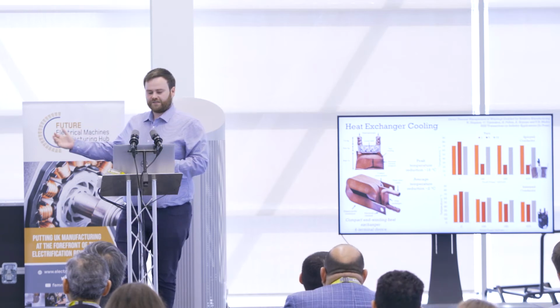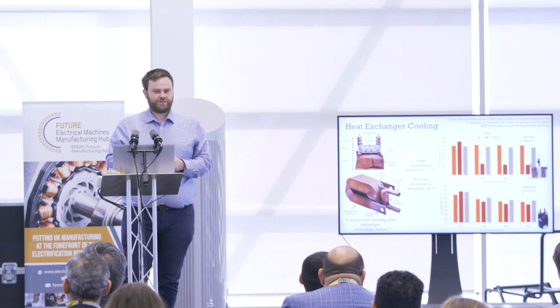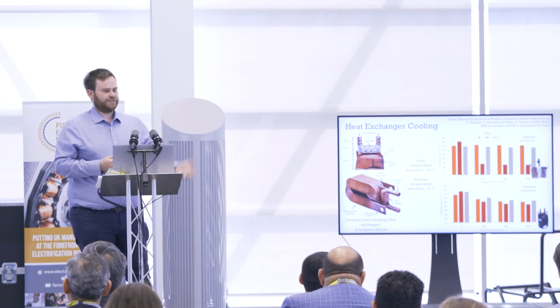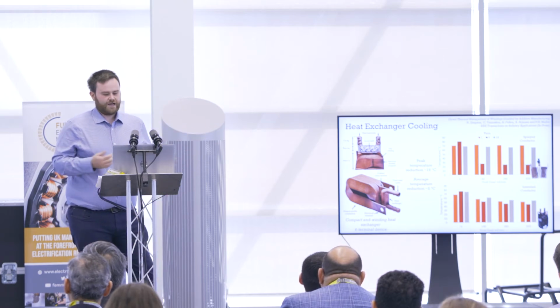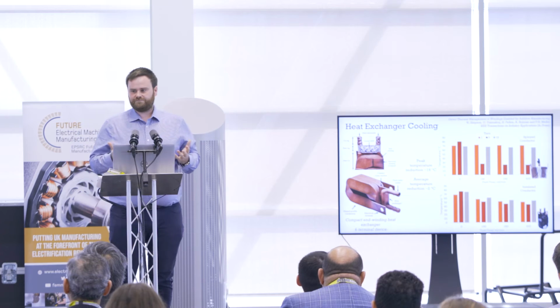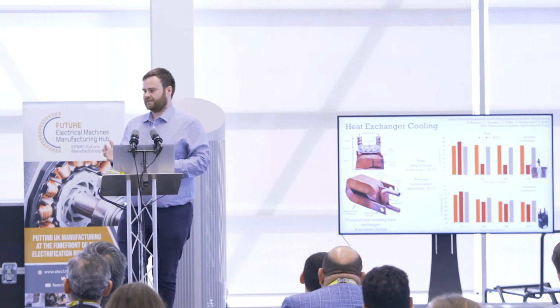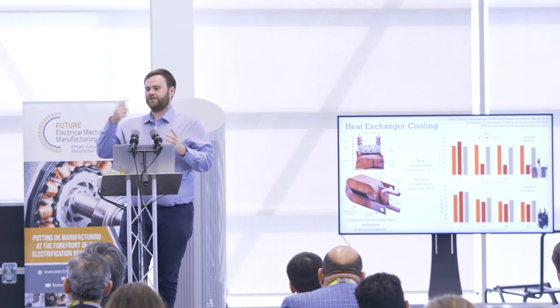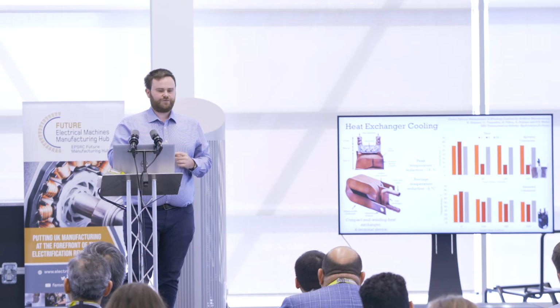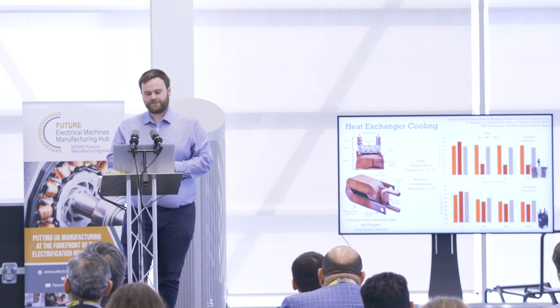So if we look at the insulated state, when we pass a fluid through it, we see that the middle turn cools significantly, as one would expect, but the outer turns see little to no real benefit. It's only through a very long conductive path, where the thermal conductive path is through the entire winding.